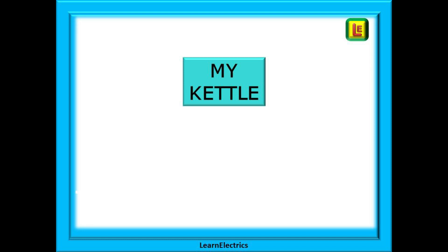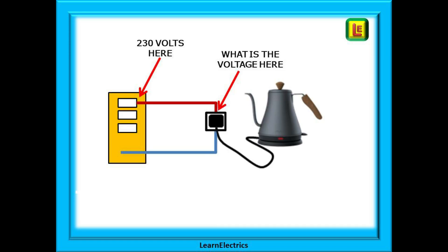Now we can apply these same methods to the kettle. The key question is: if the voltage is 230 volts at the consumer unit, what is it at the socket when the kettle is plugged in? The voltage at the consumer unit will vary from property to property and hour to hour, but we will use the nominal voltage of 230 volts as suggested in the wiring regulations for all calculations, even though many actual measured voltages are nearer to 240 volts.